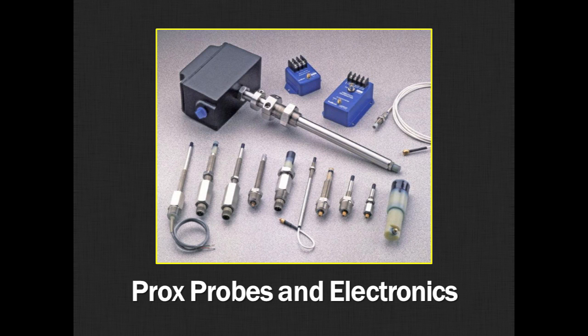Getting back to some general things here, probes that are used for vibration monitoring are typically measuring only about a hundred mils of gap. A hundred mils being about a tenth of an inch. Again, the bodies are typically stainless steel, 3/8-24 thread. The systems, the electronics, generally are outputting a signal of zero to like minus 20 volts. So we end up with a sensitivity about 200 millivolts per mil. So that's what you're measuring, 200 millivolts change in the output for every mil change in the position. Usable range of the probe is about 15 to about 85 mils. In most cases though, we're talking about vibration that's in a relatively small amount. And it may be under a mil in some special cases, but it might only be a couple of mils in other cases.